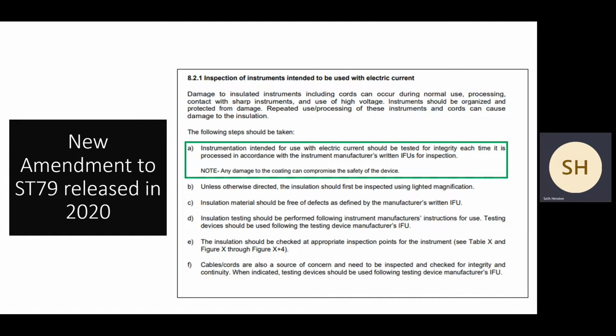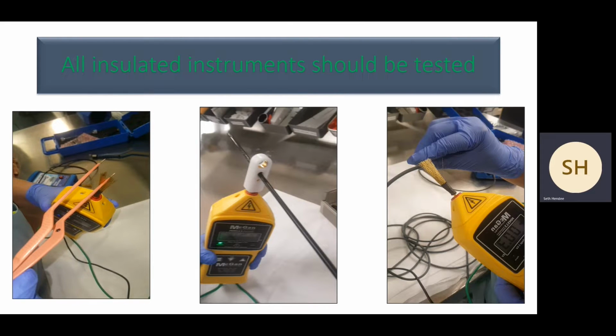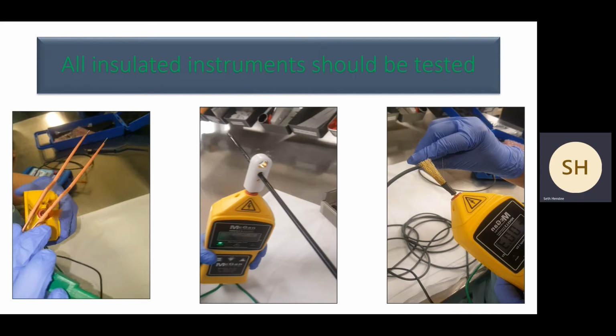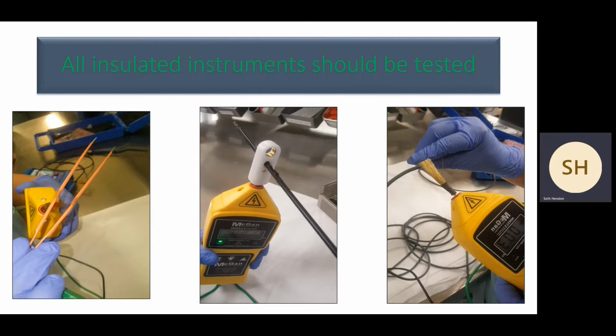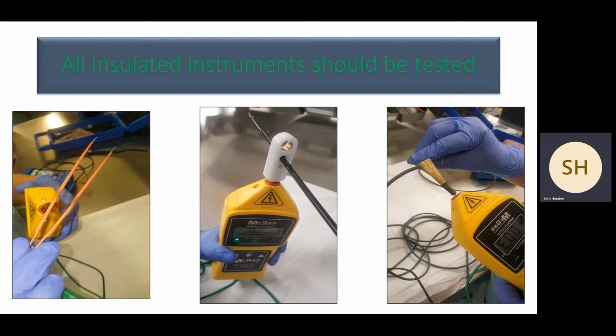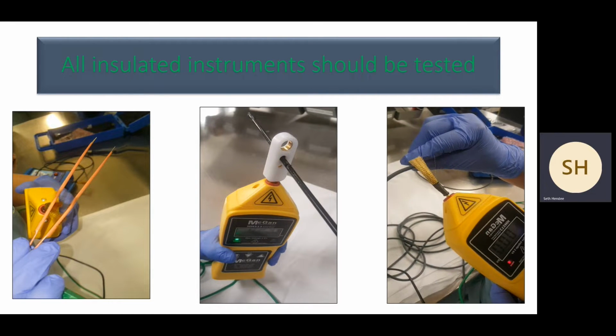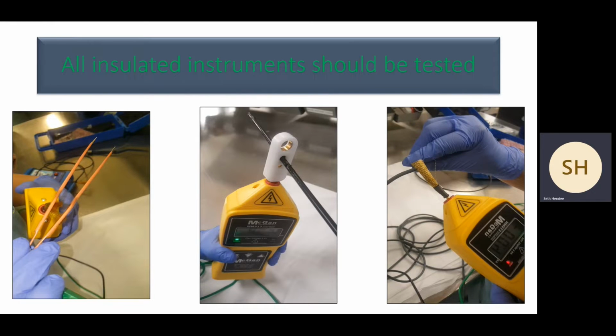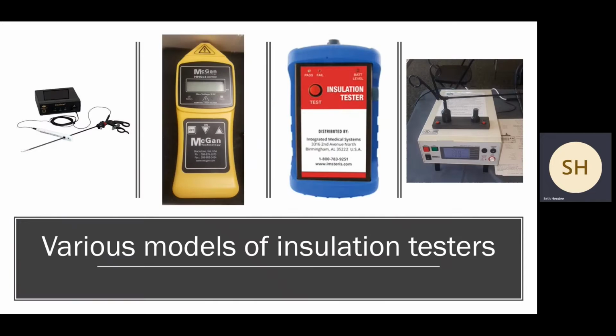And I just want to show you a quick video here. This is a bipolar forcep experiencing issues because that should be coated all the way to the tip. This is a very, very rough lap instrument that's having a hard time. And one last thing, what's your compliance with inspecting cords? Because by the way, cords are also an electrosurgical device intended to contain that energy, and they can have nicks and cuts and things like that. And many people just abuse reusable monopolar and bipolar cords. They throw them in piles. I saw an entire bin of them. They were all rubber banded into the tightest little balls that they could be put into. Well, that certainly can cause damage to your instrumentation.